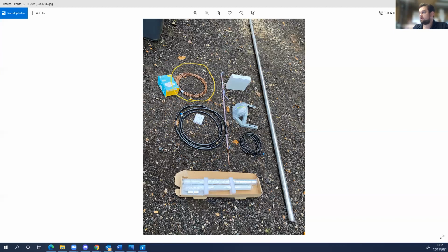This is a brown single core 12mm cable, as opposed to using the bright yellow and green. You can get it in black, but I have yet to source it. That will attach to the lightning adapter, go down to the floor, and then attach to this lightning rod, which is 1.5 meters, and I will drive that into the ground.